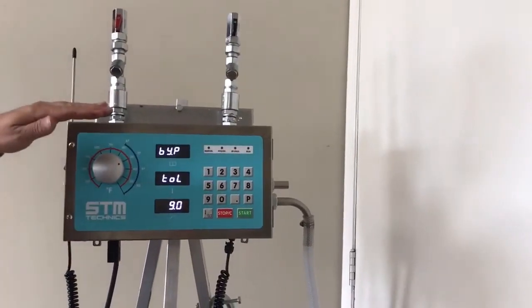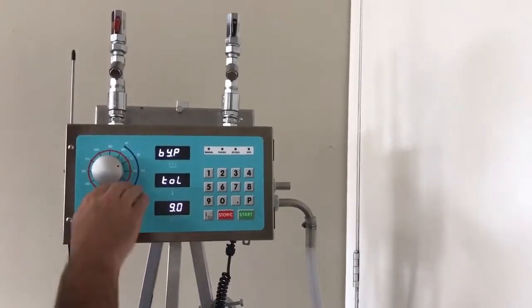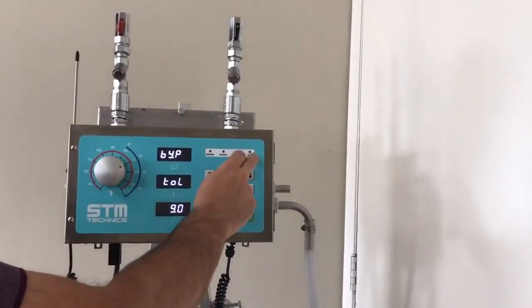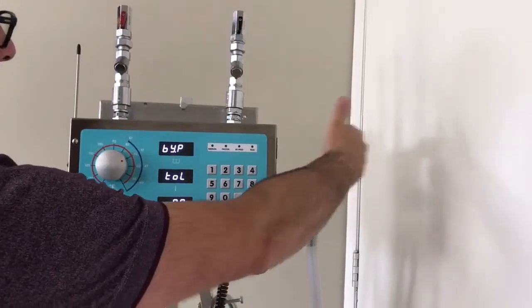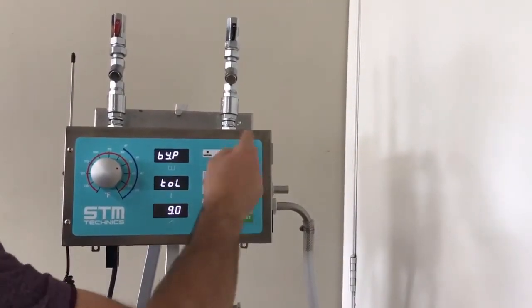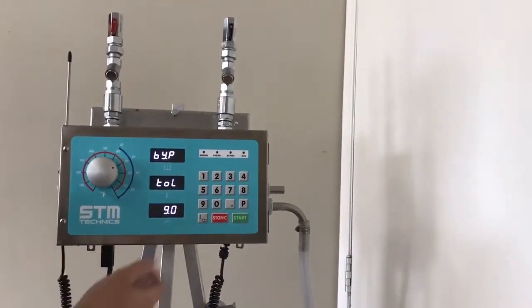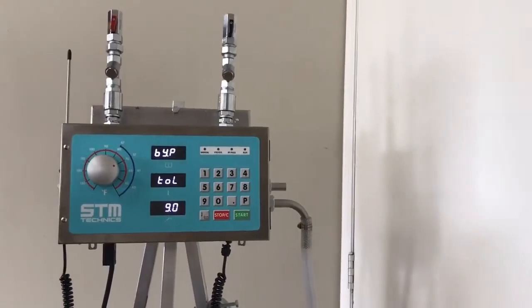If the water temperature floats 2.7 degrees above or below your set temp, the unit will jump back to bypass until that water reaches our set temp again and then switch over to run. With such a tight tolerance, this can go back and forth. So we're going to increase the tolerance to give us a little bit of wiggle room.